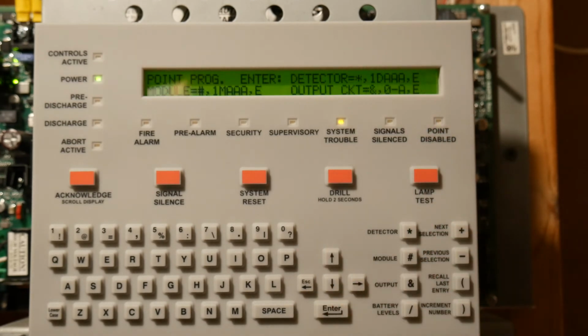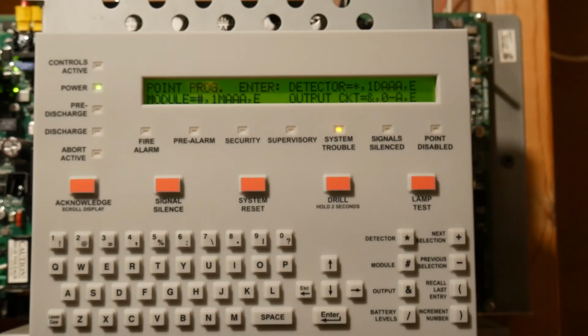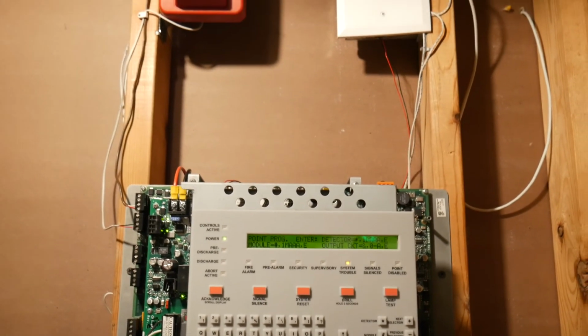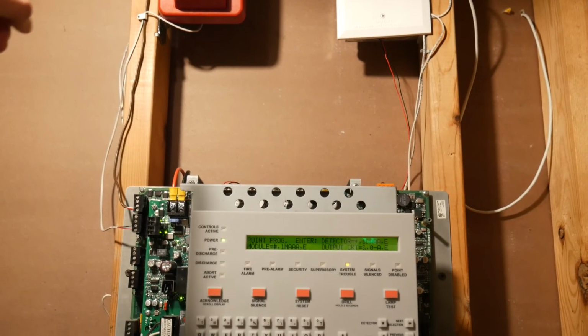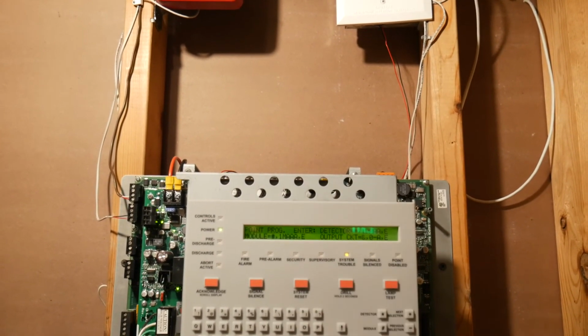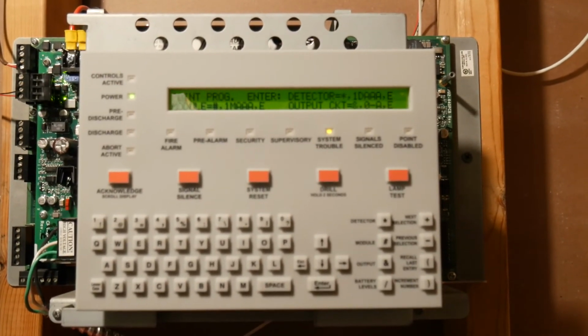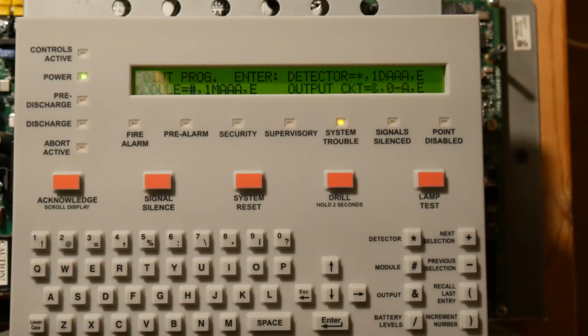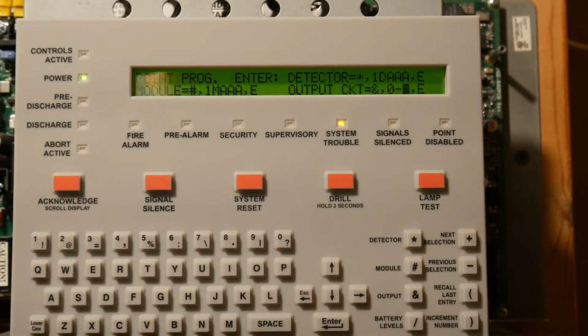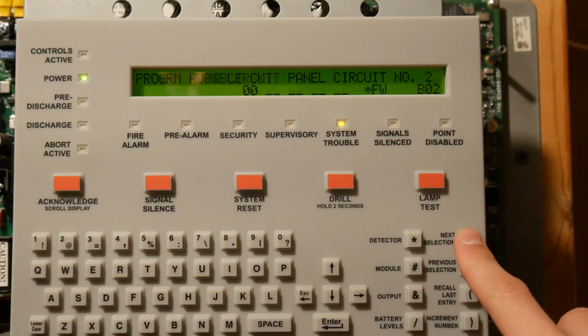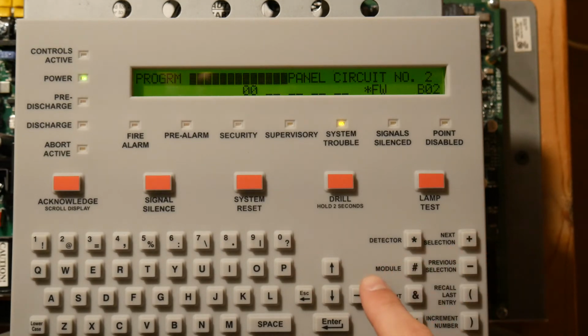And now we're going to set our agent release zone. Our agent release zone is this NAC right here. This Gentex one right here, I'm not sure if you can see it, says agent release, and it's on NAC2. So the way we change NAC2 to an agent release, we're going to go to output 2. And now we're going to set this as a release code bell.